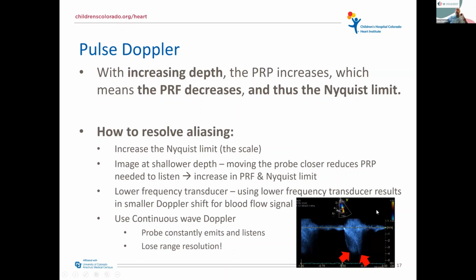Doppler. And so in continuous wave Doppler, it's continuously sending out a signal and continuously listening. But the problem is that by doing that, I can no longer say, I want to listen to that one object that's 10 centimeters away. You're listening to everything along that beam angle, and you have the ability to get really high velocities. You can see here we're over 5 meters per second. But the problem is you lose range resolution.